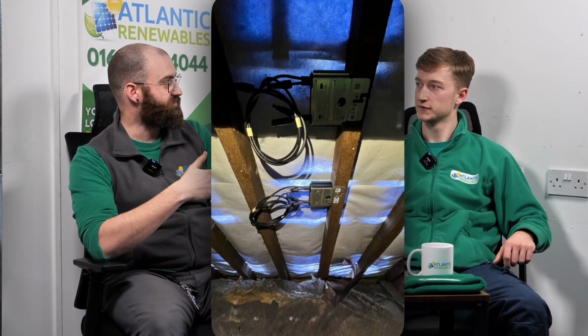So we'd only install these Optimisers if necessary, if there are shading problems, because it's technically a possible point of failure. So if we're going to fit them, it means it's really having an impact on the performance. It's going to really benefit the system, and it will be a worse performing system without, if that makes sense. But again, it's a point of failure, so it's something to design as well as we can to access them in the future. So then, just to dive into it a little bit more.